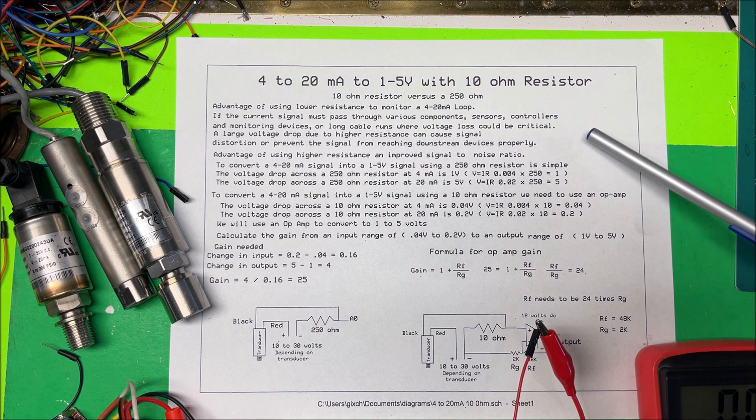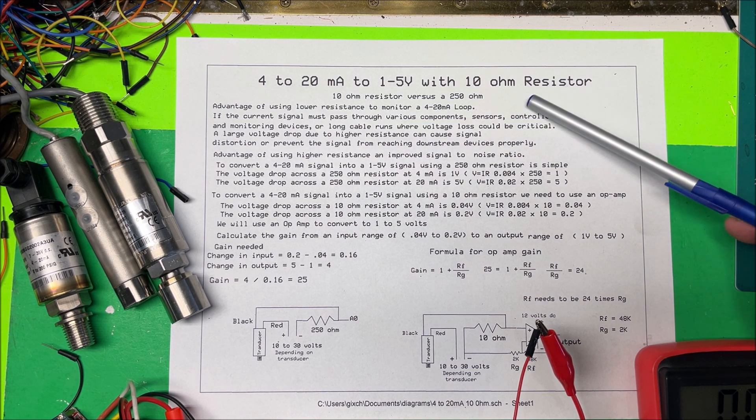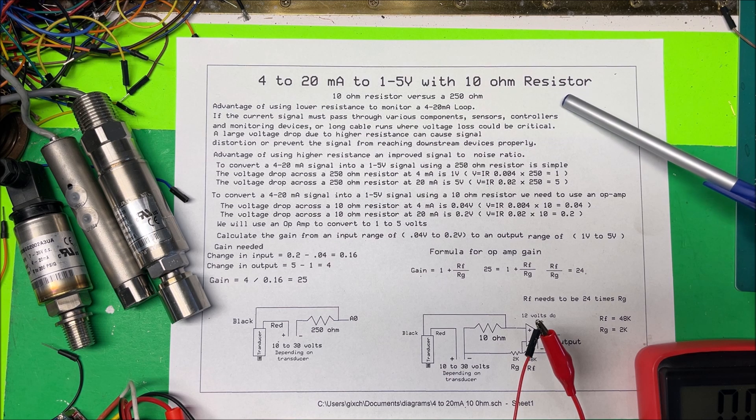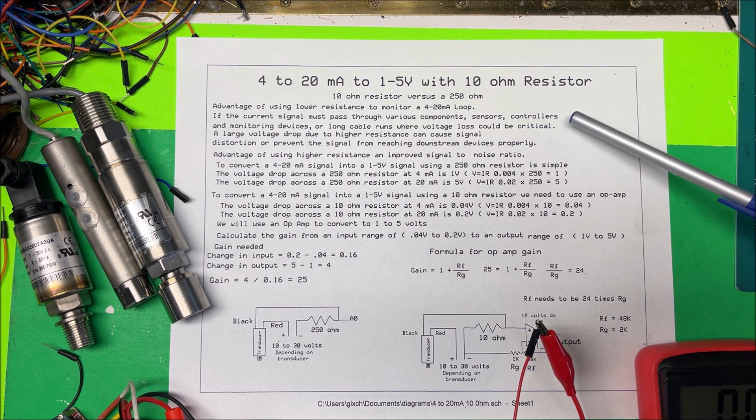Now I have gone 600 meters with a 4 to 20 milliamp loop, but that's kind of pushing the boundary on that. So we're going to try it with the 10 ohm resistor.